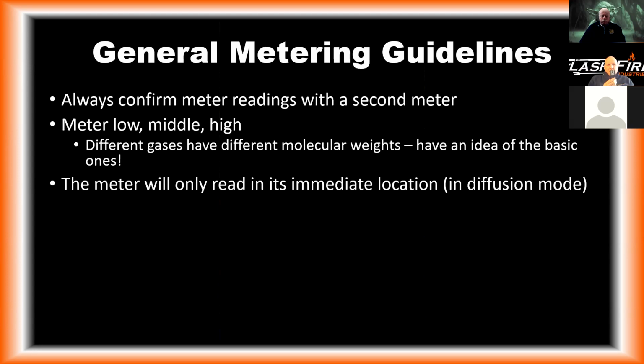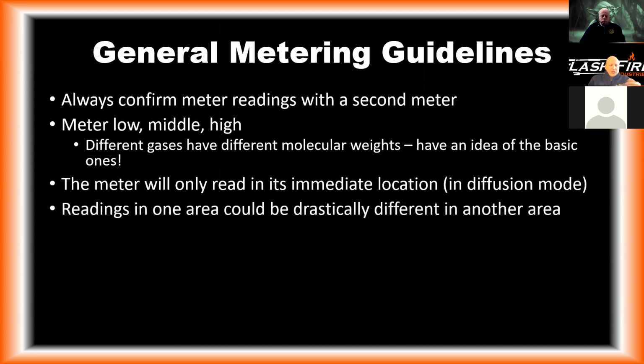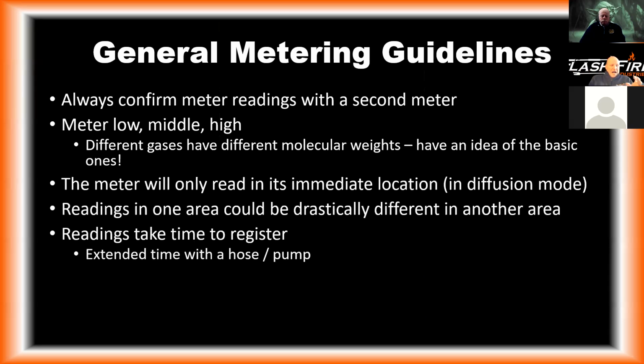Okay, so here I am on one side of my room. I'm not reading the other side of the room. So it's important that we move around and we move the meter up and down so that we're able to read in different areas of the room. Readings could be drastically different in one area than another, different rooms, or different pocket areas where gas can collect. The readings do take time to register. So the lower the readings, the more time it's going to take to register, and it's going to take even more time if we're using a hose or a pump.